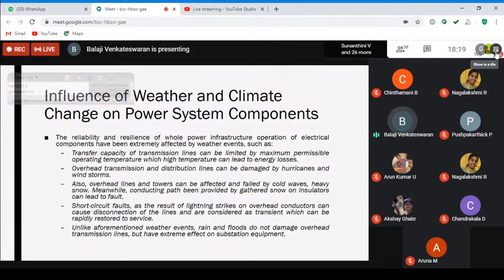The first point, as I mentioned, is that the transfer capacity of a transmission line can be limited by the maximum permissible operating temperature. When wildfires occur, and I think even in our state, Tamil Nadu, between the forests, some transmission lines may move, we may not notice, but it may be moving. If a forest fire or wildfire catches, the temperature is going to increase in the surrounding areas, which gets transferred into the conductor also. So the temperature increases, and the maximum permissible capability of that particular line, which was earlier there, is reduced because of the wildfire. This is one example for the first point.